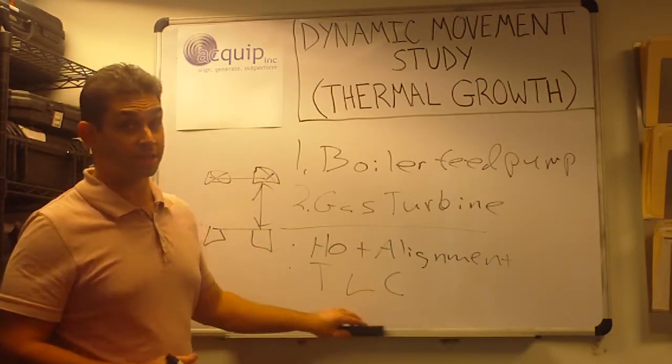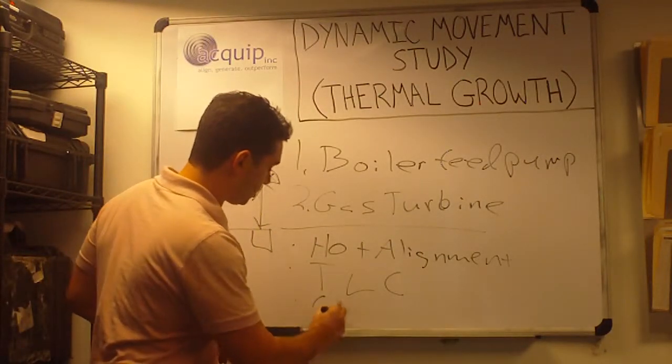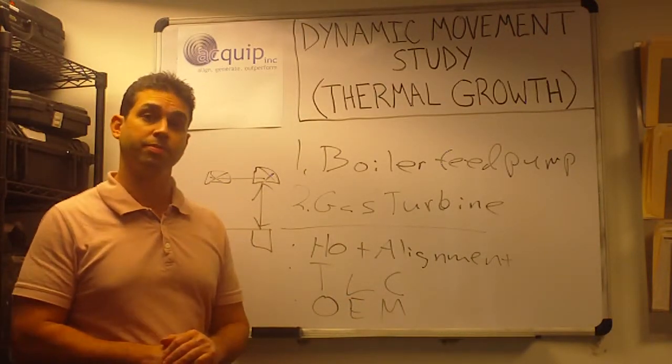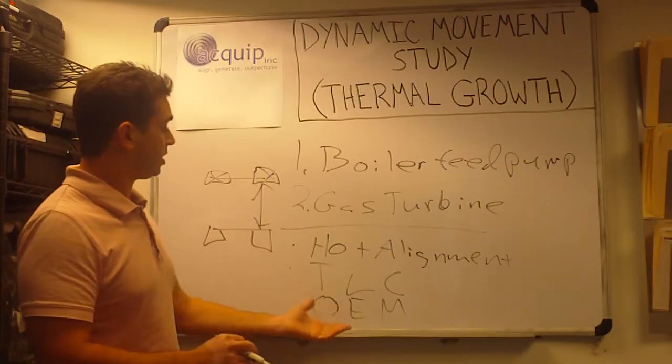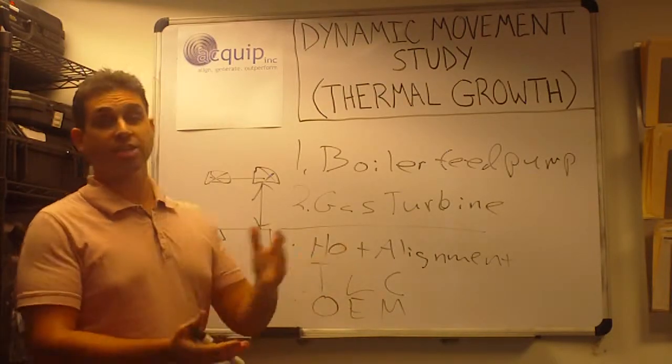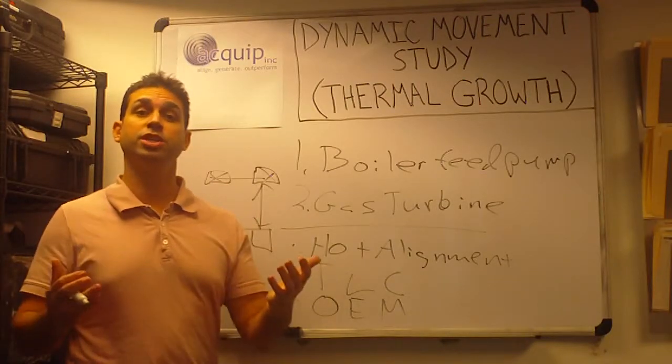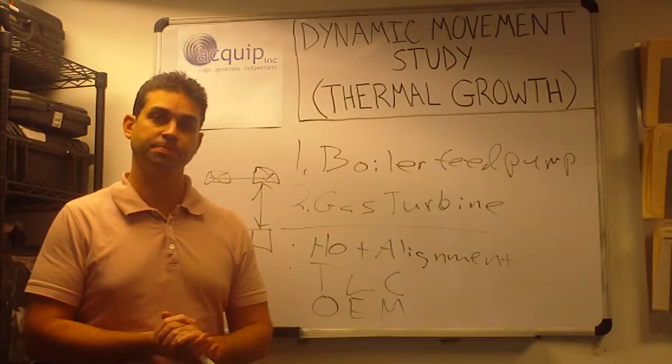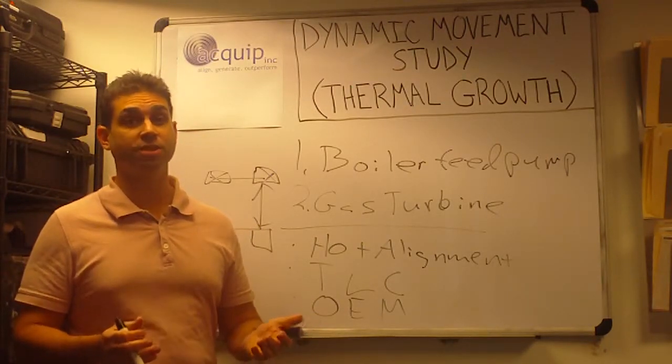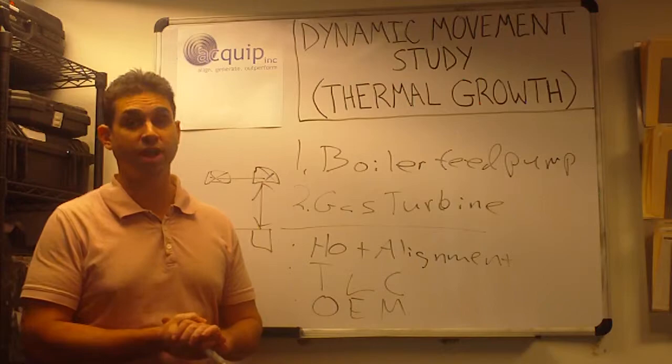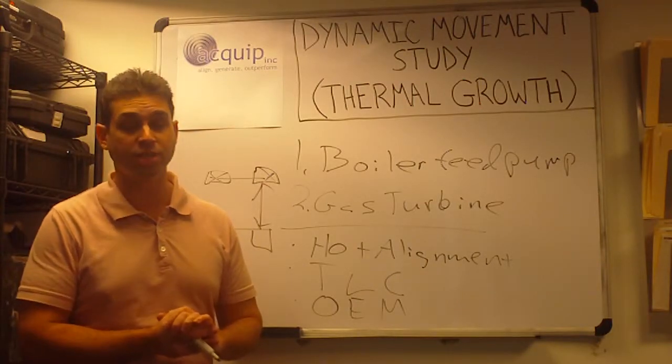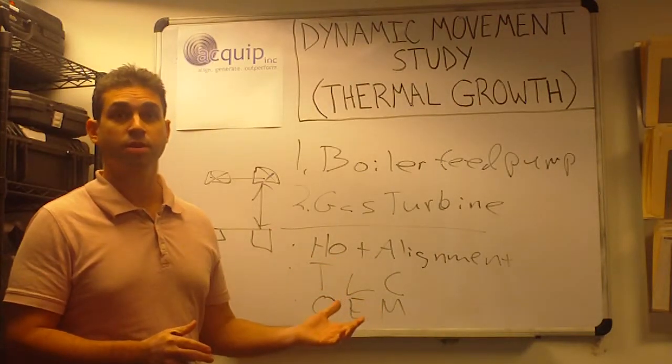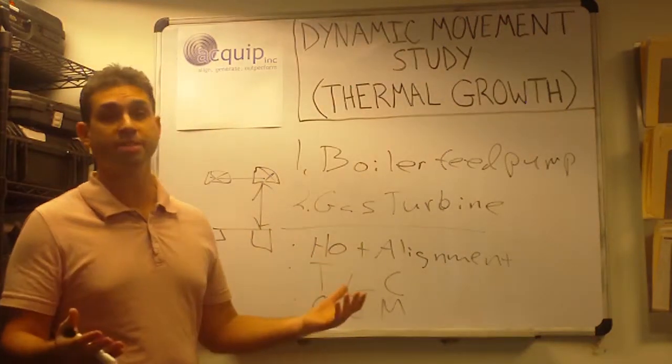The third thing that we do is a specification from the OEM. The specification given to you by the OEM is on their machine, in their facility, under their operating conditions, and in their environment, which is going to be different than your machine, in your environment, under your piping geometry, and your specifications. So, it's better than doing nothing, but it's not the best thing we can do.